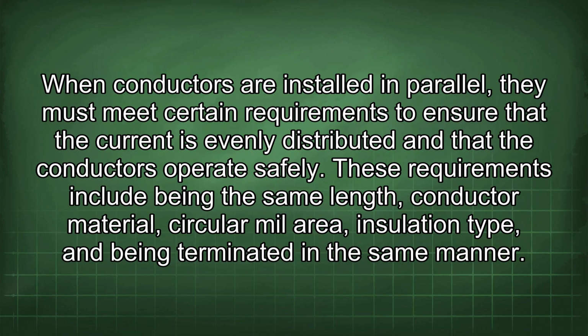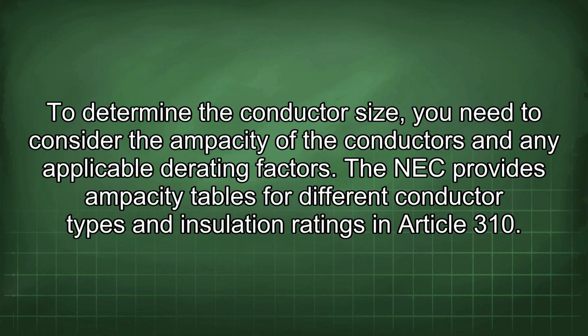When conductors are installed in parallel, they must meet certain requirements to ensure that the current is evenly distributed and that the conductors operate safely. These requirements include being the same length, conductor material, circular mil area, and insulation type, and being terminated in the same manner. To determine the conductor size, you need to consider the ampacity of the conductors and any applicable derating factors.